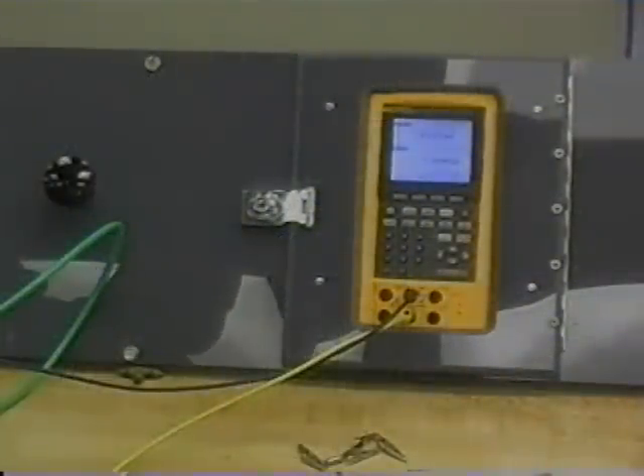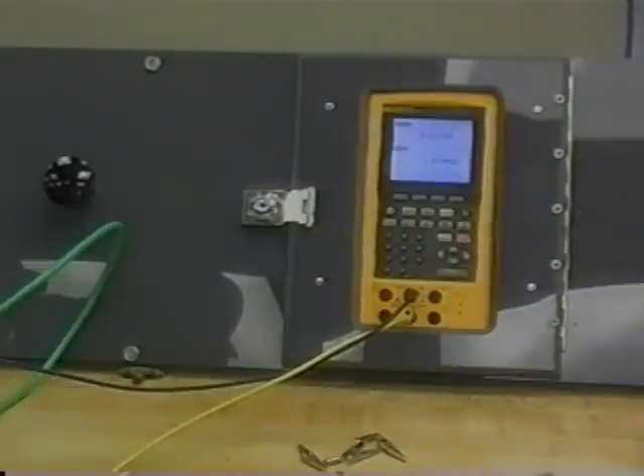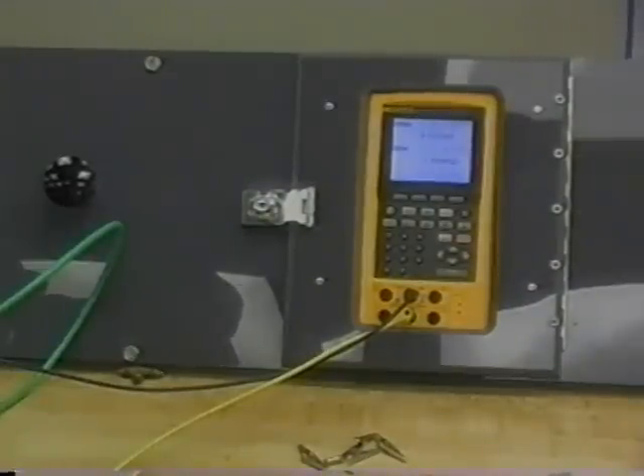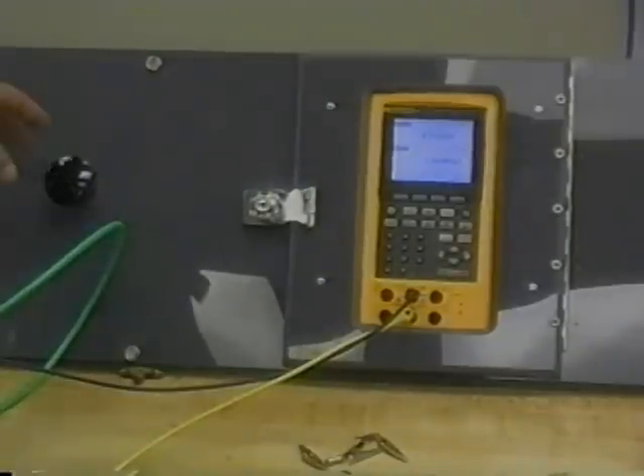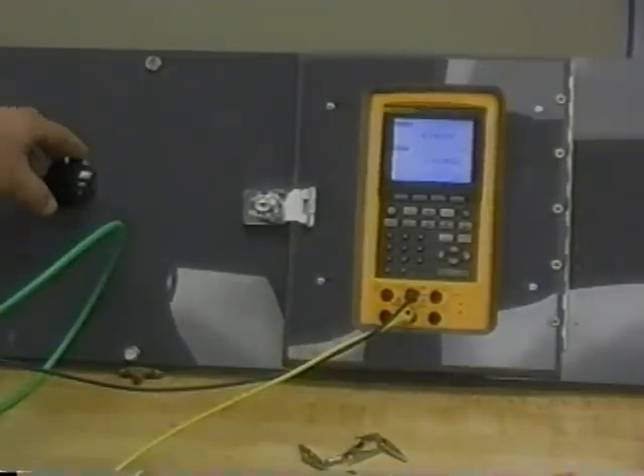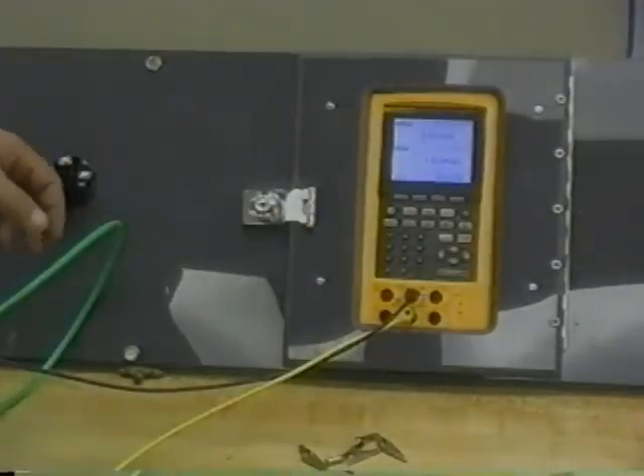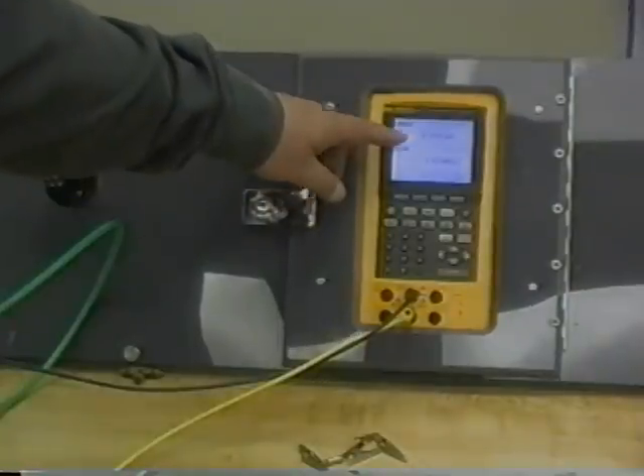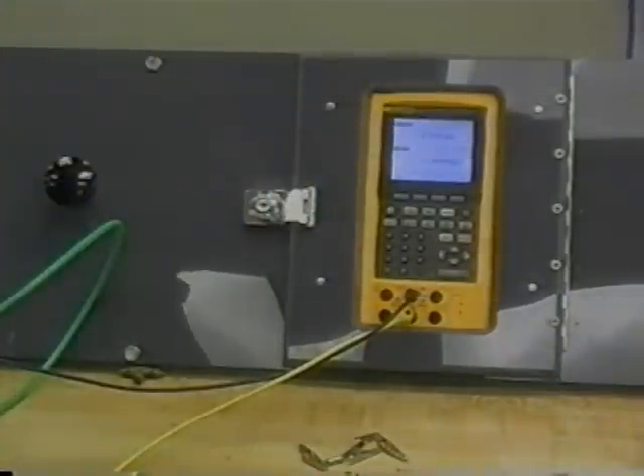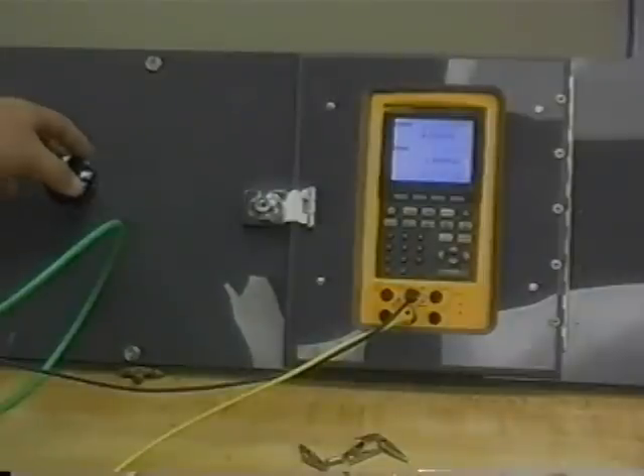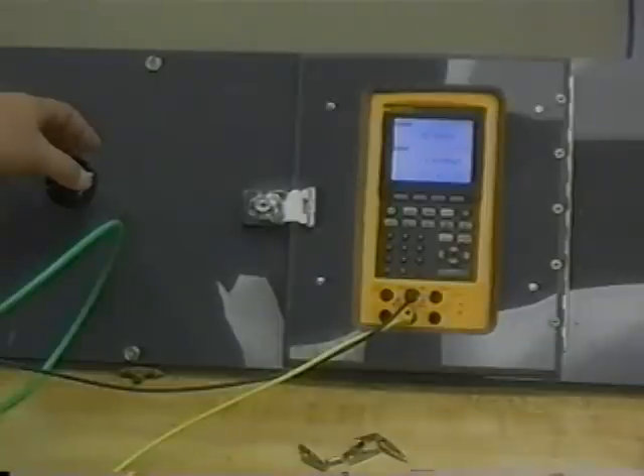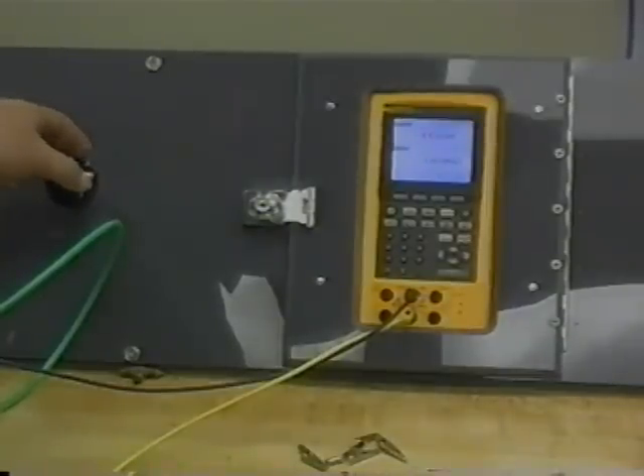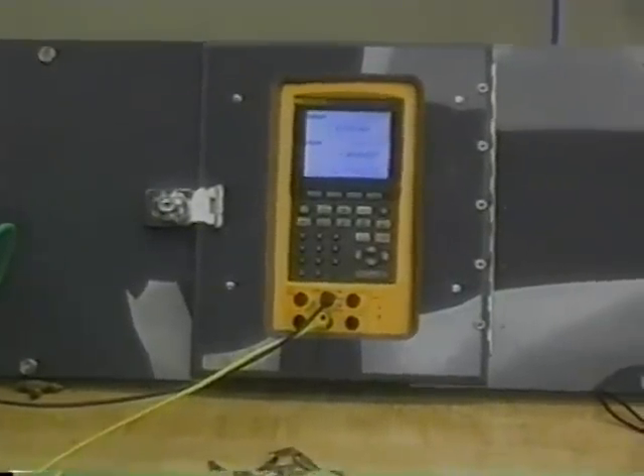After completing the calibration, we need to test it by running the pressure up and down scale inside the transmitter and taking a look to see what the analog output is. To do that, we're going to use a high-precision regulator and the Fluke 744 documenting process calibrator to see what the pressure is and to see what the output from the transmitter is. By turning the regulator to the right, you can see that the pressure is starting to increase.